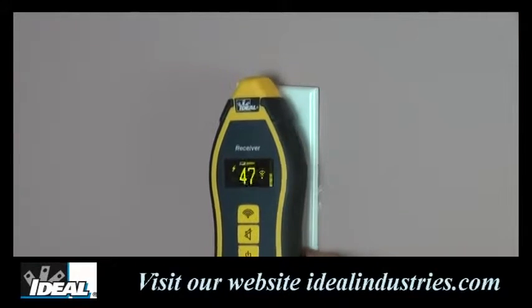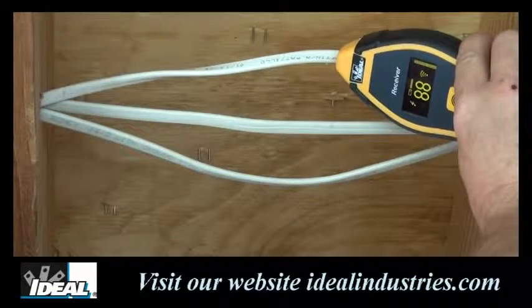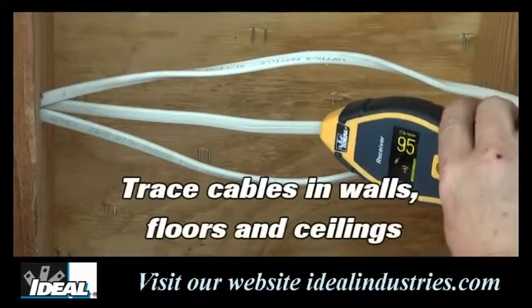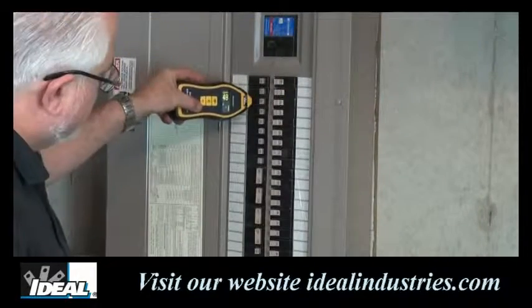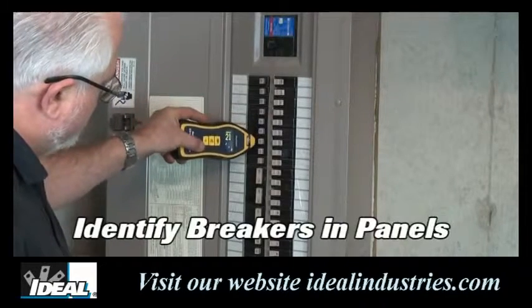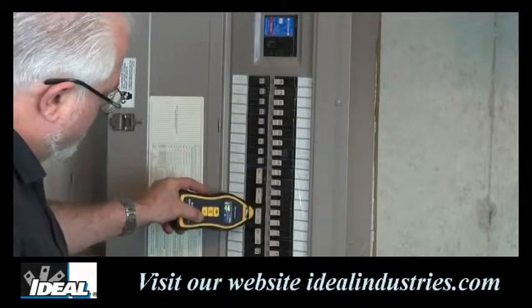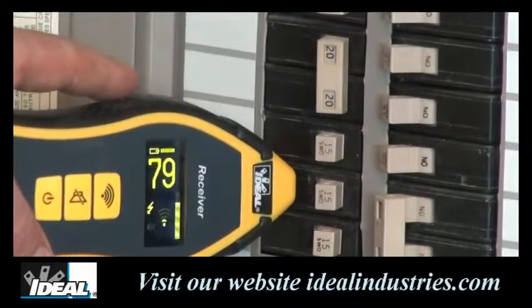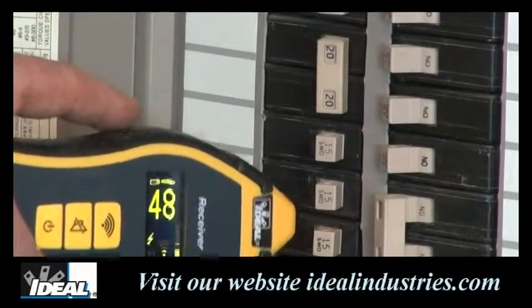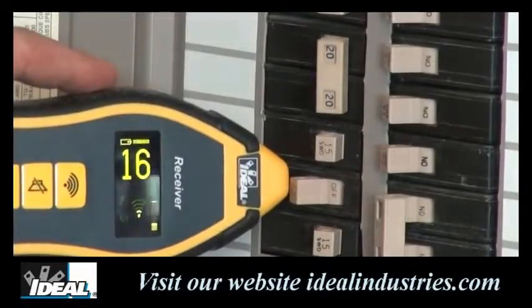The receiving unit can locate other outlets nearby that are tied directly into the same circuit, as they will give a very high reading. You can trace cabling in walls and ceilings looking for cables that give the highest reading, and trace all the way back to the electrical breaker panel to properly identify the breaker by scanning with the receiving unit and looking for the highest reading. Once identified, you can trip that breaker and the lightning bolt symbol will turn off on the receiver, indicating the transmitting unit no longer detects power on the circuit — confirming you tripped the right breaker.